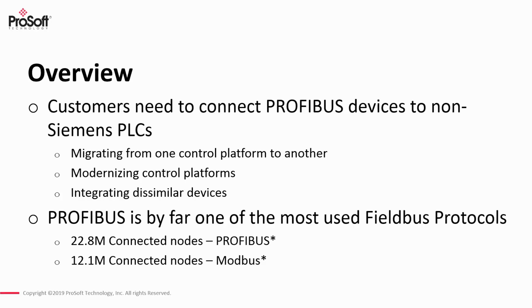We can also utilize PROFIBUS modules when looking to modernize some control platforms. If you've got legacy systems out there that are using PROFIBUS, you can bring those into a newer control architecture that's potentially supporting EtherNet/IP or Modbus TCP/IP, and modernize some of those architectures.